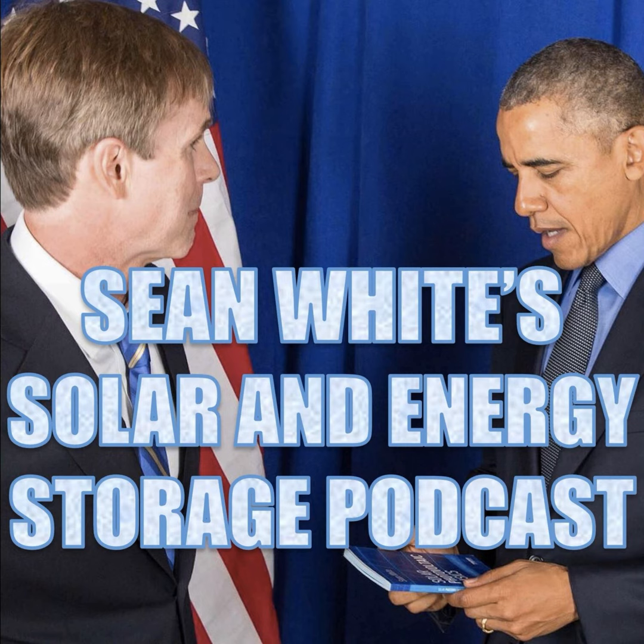That Enphase battery was an AC coupled system, just like the Tesla Powerwall you can buy these days, called the Powerwall 2, which we're going to talk about now. The Powerwall 2 would be used with a backup gateway, which is your anti-islanding device, also known in the National Electrical Code as a microgrid interconnect device.